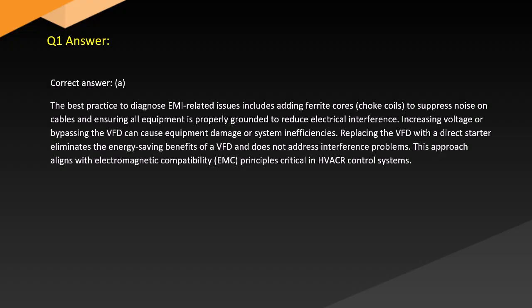Answer. Correct answer: A. The best practice to diagnose EMI-related issues includes adding ferrite cores and choke coils to suppress noise on cables, and ensuring all equipment is properly grounded to reduce electrical interference. Increasing voltage or bypassing the VFD can cause equipment damage or system inefficiencies. Replacing the VFD with a direct online starter eliminates the energy-saving benefits of a VFD and does not address interference problems. This approach aligns with electromagnetic compatibility (EMC) principles critical in HVACR control systems.